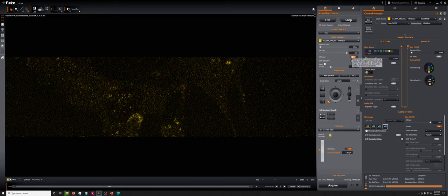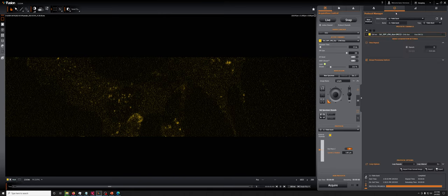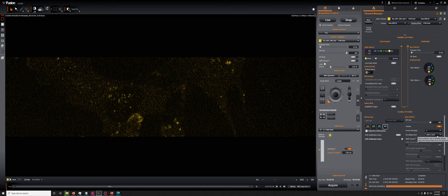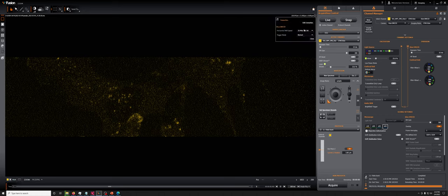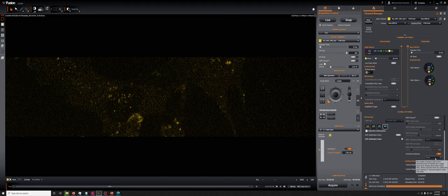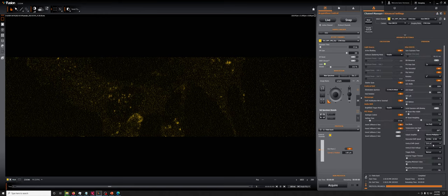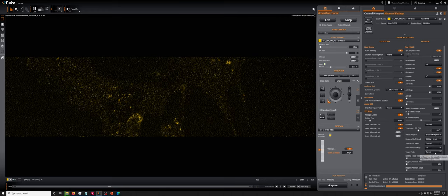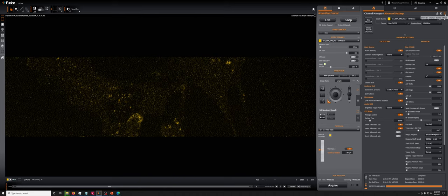So to recap, how do we ensure that we can go as fast as possible with the Ixon camera? We want to make sure we're in a finite burst protocol. We want to make sure that we use cropping. So instead of the default 1024 by 1024, we want to use cropping. We want to make sure that we're in the horizontal shift speed of 30 megahertz instead of 10 megahertz. And we can bin the camera if we can get away with that reduction in resolution. And finally, we can adjust the vertical shift speed from the normal, which is 2.2, and the vertical clock voltage from the normal to respectively 0.6 microseconds and plus one. And that can help us go faster. Though these vertical clock voltages and vertical shift speeds here in the advanced camera settings, I would only go there as sort of a last recourse.